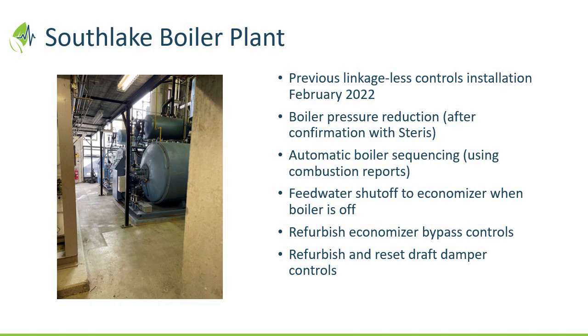Now we're looking at boiler pressure reduction, and the hospital is rightly just making sure that the sterilizers are comfortable with that, looking at automatic sequencing of boilers, and we'll be asking, again, I think Paul with Brent's color commentary and John's kind of contribution from the left. So automatic sequencing as opposed to the operators deciding which boilers to run when, typically in pairs. The shutting off the feed water supply to economizers when the boiler's not running, so effectively they're not giving the heat back from the condensate going in there. The economizer bypass controls and the draft dampers are questionable.